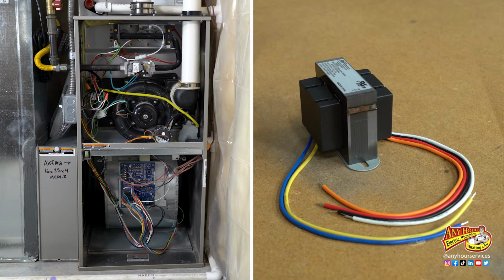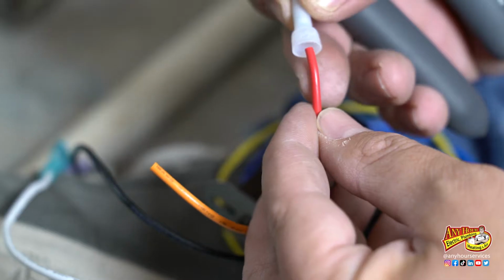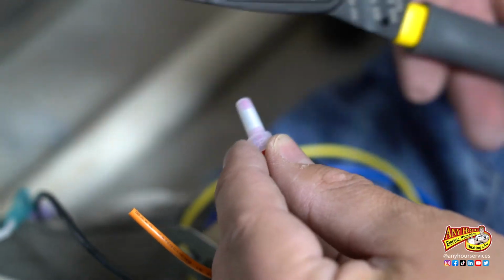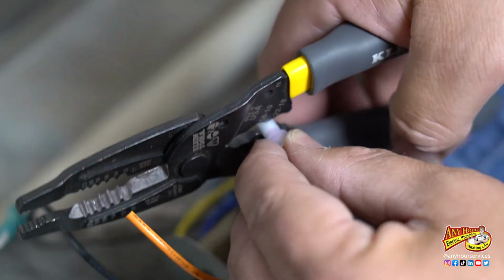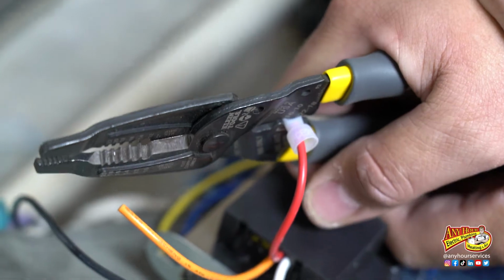This is a standard 120 volt furnace, so we'll be using the black and white wires on the high voltage side of the transformer. If your furnace is a different voltage, adjust how you wire up the transformer accordingly. I find it easier to prepare my connections before I mount the transformer. I'm going to trim and cap off the wires that I'm not going to be using.